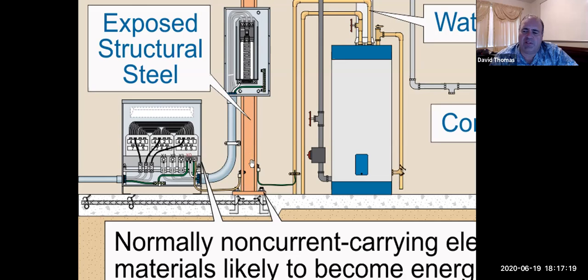Anyway, most of these buildings, what I was talking about is the structural steel. If it's bolted into the ground, it's a solidly bolted type system. The ones that I'm talking about that are floating are like buildings in downtown San Francisco, downtown Oakland even has some, LA, where literally you'll see these buildings that are not solidly grounded, attached to the earth or to the ground. So the beams, you have to put a little bit more thought. Usually you put a jumper from one side of the beam down to earth. So there's ways to ground it. And as long as your beams are properly grounded, you can use that as a pathway to bond everything.